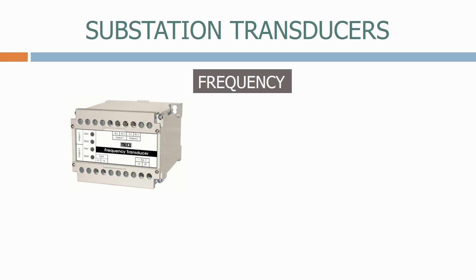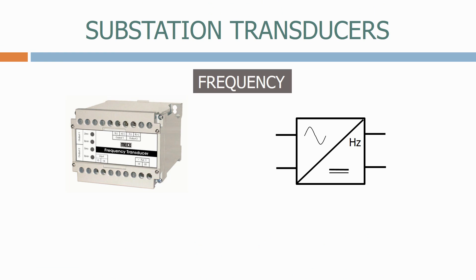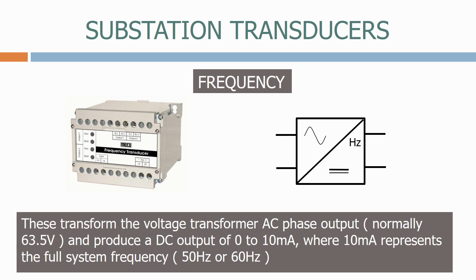Next we have a frequency transducer. This is the symbol we normally use. These transform the voltage transformer AC phase output, normally 63.5V, and produce a DC output of 0-10mA, where 10mA represents the full system frequency, either 50Hz or 60Hz.